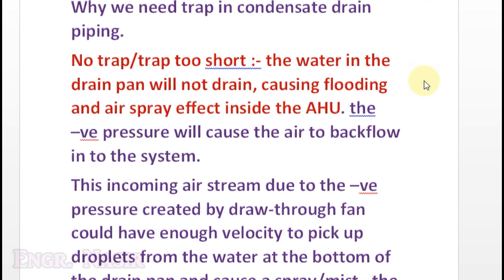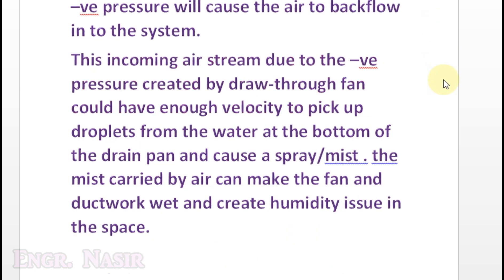Why do we need a trap in condensate drain piping? If there is no trap or the trap is too short, the water in the drain pan will not drain, causing flooding and an air spray effect inside the AHU. The negative pressure inside the drain pipe will cause air to backflow into the system. This incoming air stream, due to the negative pressure created by the draw-through fan, can have enough velocity to pick up droplets from the water at the bottom of the drain pan and generate a spray or mist. The mist carried by the air can make the fan and ductwork wet and create a big humidity issue in the space being served.